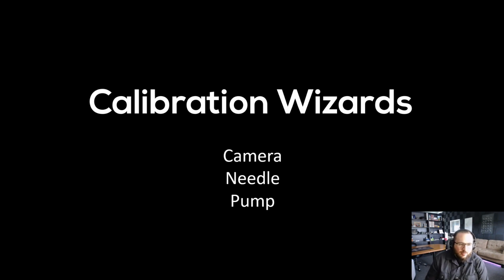Okay. Next. Now here is where we're going to calibrate the system. You're going to tell it exactly how much you want to dispense. So let's say you wanted to dispense 1.07 grams. You type that in, number 1. Now, you're going to hit cycle pump, and it is going to dispense once into this catch container, which we have tared out from a previous step. You're going to type in exactly how much it dispensed. So let's say it dispensed 1.18 grams. Type that into the second box and hit next, and the system has internally recalibrated itself so that it will always dispense the exact amount you typed in the desired box. And you can verify that now by hitting cycle pump and measuring it again.